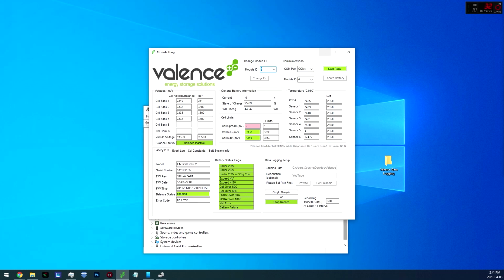If you have a bank of 20 batteries and they all have the ID of 1, when you hit start read on module 1, you're going to get discombobulated data. It'll be getting signals from all these different batteries, so the values will keep changing as it reads each RS485 transceiver, since they each share the module ID of 1. So you want to go through your group of 20 batteries and change each one to have its own individual ID, probably in consecutive order from 1 to 20.